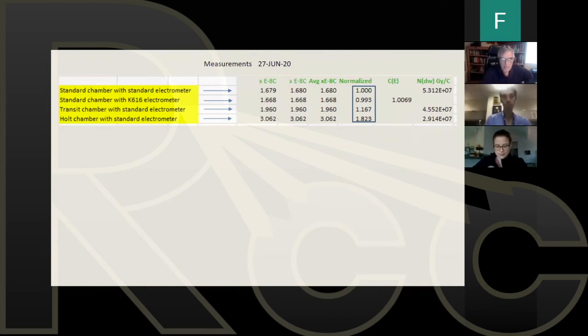So I substitute the different electrometer with the standard chamber. And I find out that one electrometer is 0.7% different from the other. I can use that factor if I use the alternate electrometer. If I want to use my transit chamber with the standard electrometer, the difference is 17%. So I correct my NDW to show that. And if I want to use the Holt chamber with the standard electrometer, it's very, very different. Look at the magnitude and difference in reading. So this becomes my new NDW if I decide to use the Holt chamber.